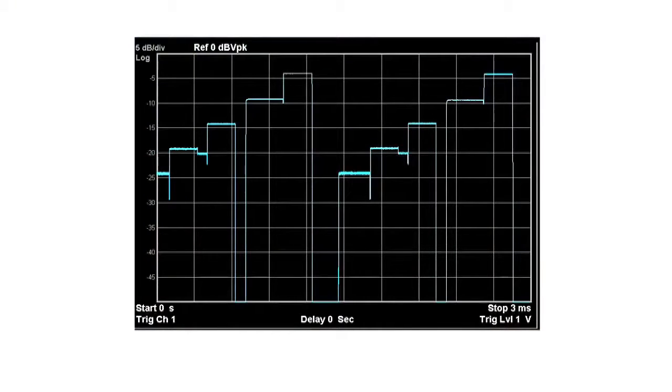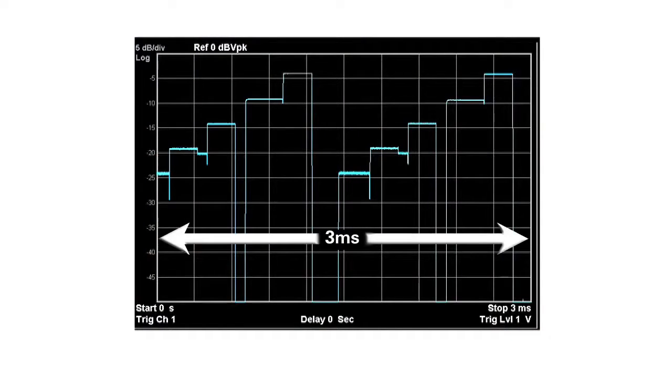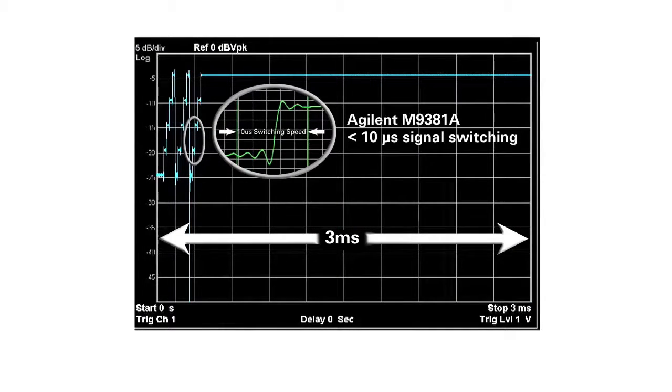Before the M9381A, amplitude and frequency switching speeds were in the hundreds of microseconds. With the M9381A, we've taken that way down to less than 10 microseconds.